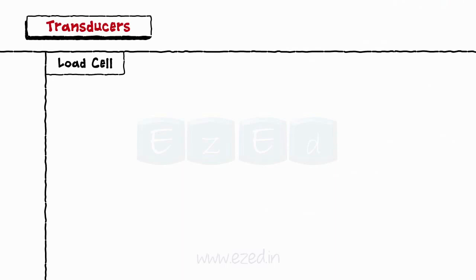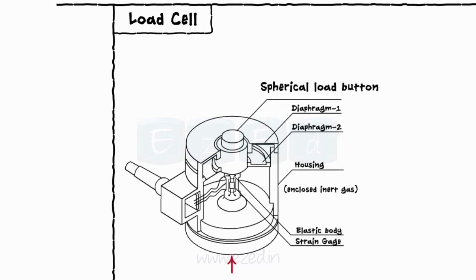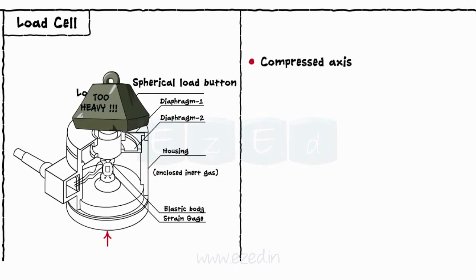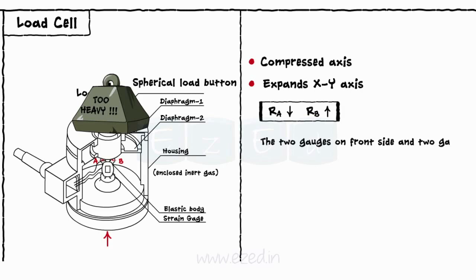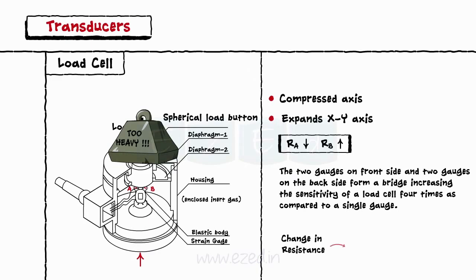The next type of transducer is a load cell transducer. As the name suggests, a load cell is used for weighing extremely heavy loads. Load cell uses a strain gauge for measuring the weights. The weight or load is applied along the direction shown by the arrow. Due to the stress of the load, the steel bar gets compressed along the vertical axis and expands along the XY axis. Due to this, the resistance of strain gauge A will decrease and resistance of strain gauge B will increase. The two gauges on the front side and two gauges on the back side form a bridge, increasing the sensitivity of the load cell four times compared to a single gauge. Change in resistance of the strain gauge produces the required output signal and correspondingly determines the weight of the load.